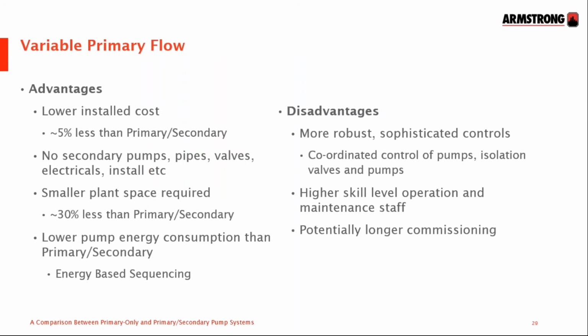Variable primary, with fewer pumps, is less expensive, roughly about 5% less in total cost than a primary secondary system. It requires less space and less equipment because there are fewer pumps, and it draws less power. The chillers working at part load are more efficient, and you can get some good energy-based sequencing, and it lends itself to chiller plant optimization.